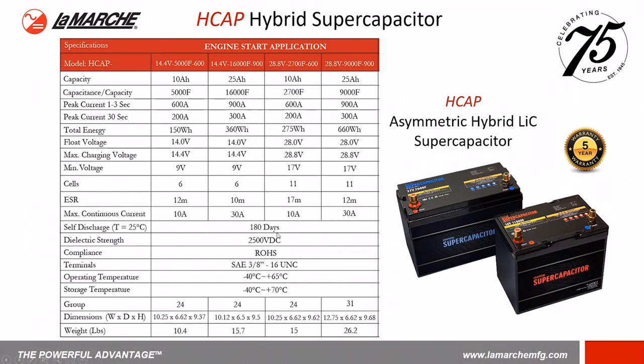The other nice thing is the self-discharge on these is about 180 days, so you can leave them in storage and still be at their highest performance even 180 days later. And the wider temperature range that I mentioned earlier, which is minus 40 degrees C to plus 65 degrees C. Along with the weight: as you can see, a 28-volt module weighs only 26 pounds versus a 4D or an 8D battery weighing around 80 to 100 pounds.